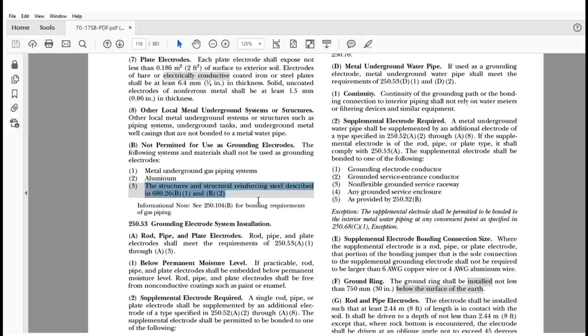Now, this is a list of what is not permitted for use as a grounding electrode. We're very familiar with 1 and 2. The first one was metal underground gas piping. It has nothing to do with bonding the gas lines inside the building. It has everything to do with using a gas line or gas piping as an electrode. There's a difference between bonding to the gas system and actually using it in the ground as an electrode. I'm sure we all understand that. That's been hammered home to us for many years in that application, right?